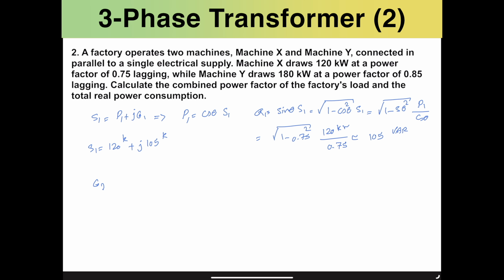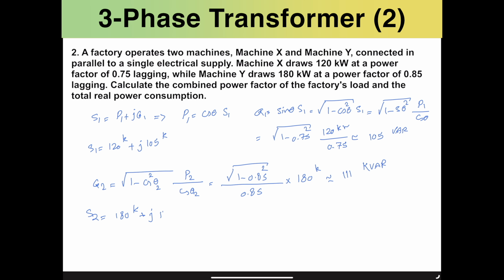Now let's move to the second machine. We'll employ the same line of thought for Q2, borrowing the same equation: square root of 1 minus cos theta squared, divided by cos theta, times P2. Here cos theta is 0.85 and P2 is 180 kilowatts. So we get square root of 1 minus 0.85 squared, divided by 0.85, times 180 k, which gives around 111 kvar. And essentially S2 now becomes 180 k plus j111 kvar.